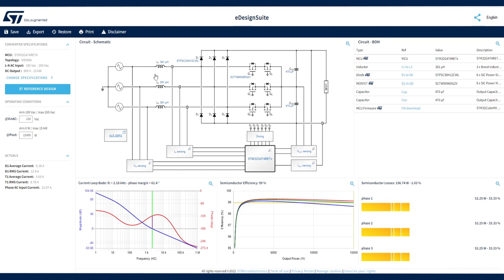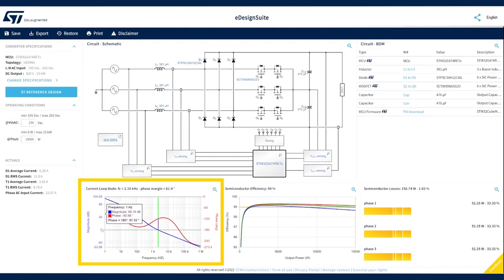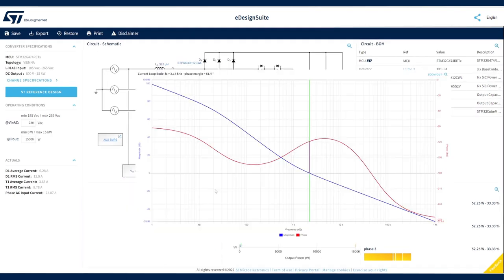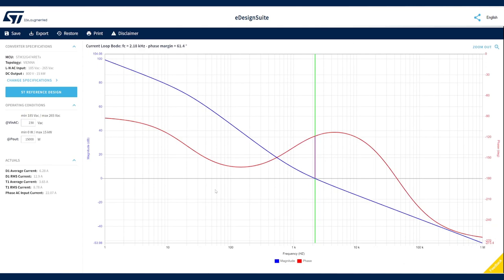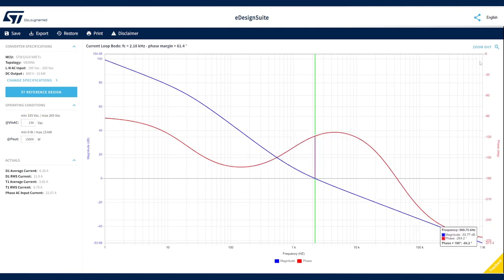At the bottom of the dashboard, you'll find a current Bode diagram showing the current regulator magnitude and phase margin performance. This diagram is useful for assessing loop stability of the power factor correction.